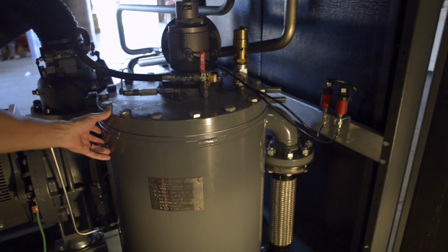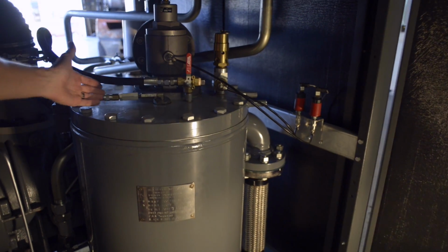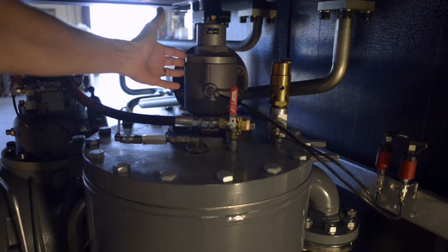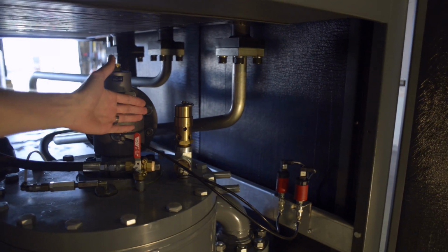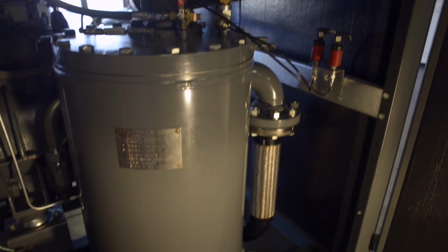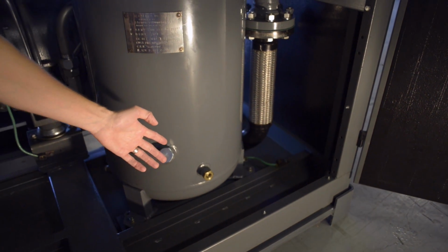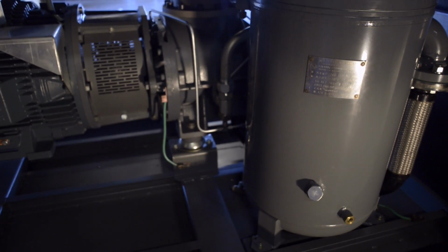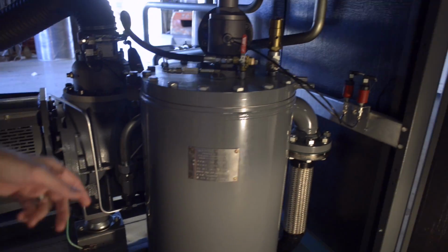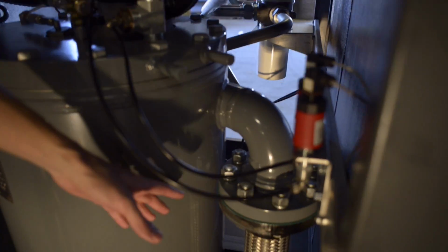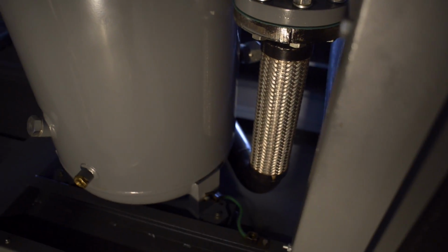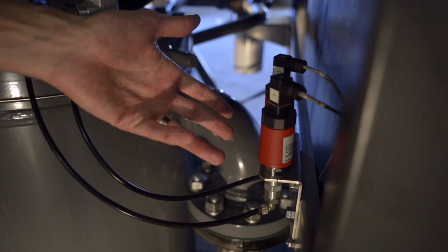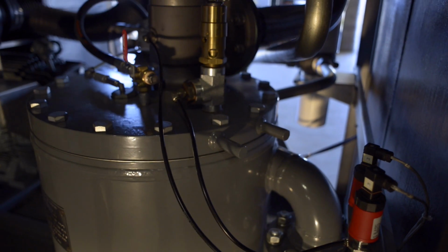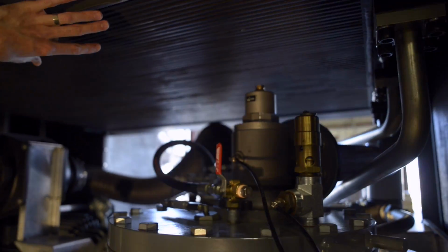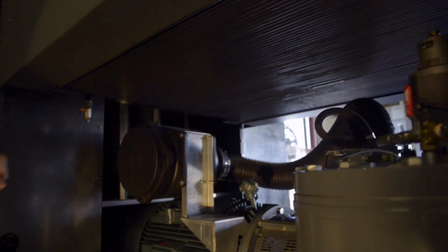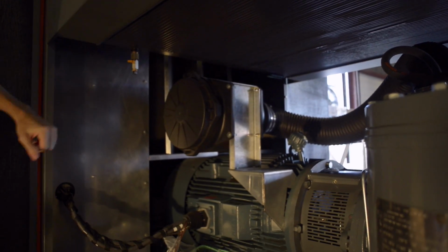So moving along here, we have the air oil separator filter with the scavenge line. There's a minimum pressure valve and the safety valve and three-way service valve. You have the oil cap and sight glass and the drain at the back. On the right there, you see the braided flexi hose and the two pressure transducers, one for line pressure and the other for the pressure drop across the separator filter. And at the top, you see the heat exchanger with the drain on the left there.